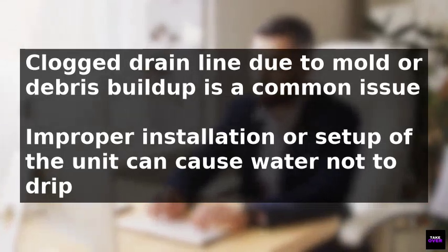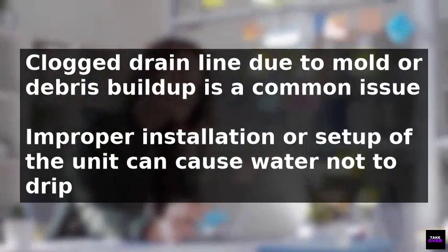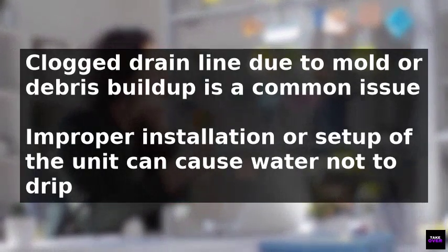To fix an air conditioner that's not draining water, there are several possible causes to consider. Firstly, a clogged drain line due to mold, dirt, or debris buildup is a common issue, which can be resolved by using a wet-dry vacuum to clear the clog.